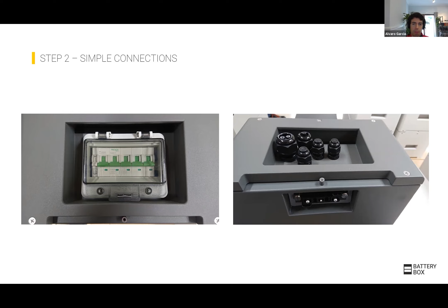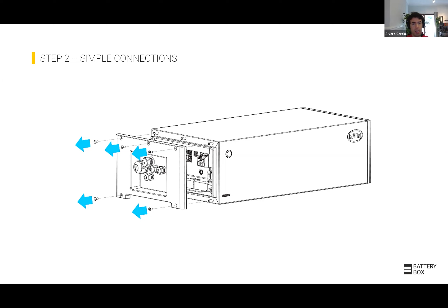And then one of the new things we have added to the premium batteries is the single point of connection. So we wanted to make it really easy for the installer to know exactly where to do all the connections, plus at the same time, make sure that they're always operating the system safely. So there is only a possibility to switch on the battery when the cover is closed. So as soon as you open the cover, there will not be any live voltage in the battery system.